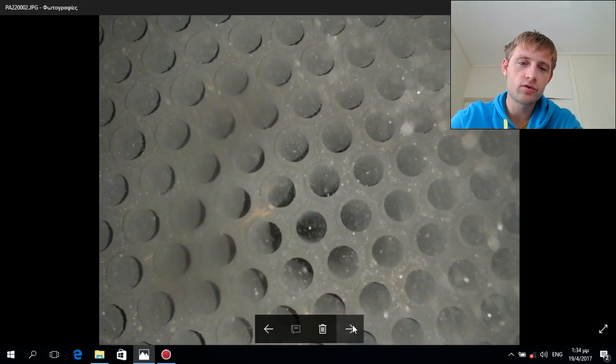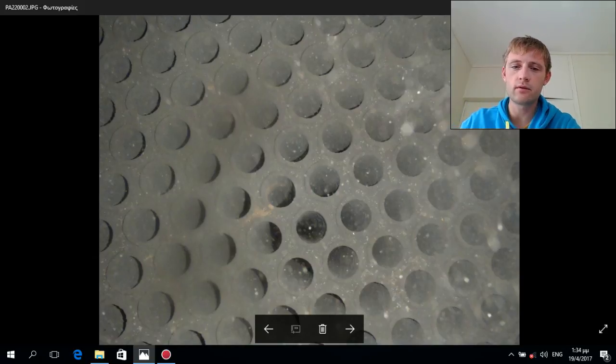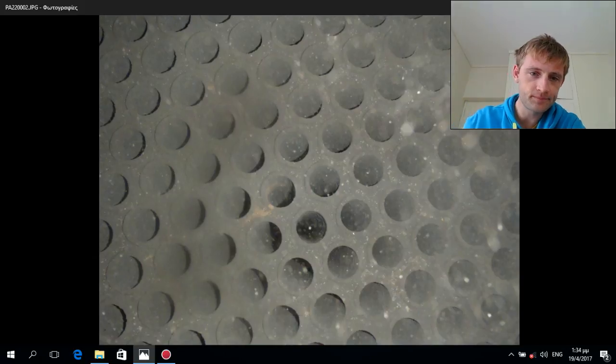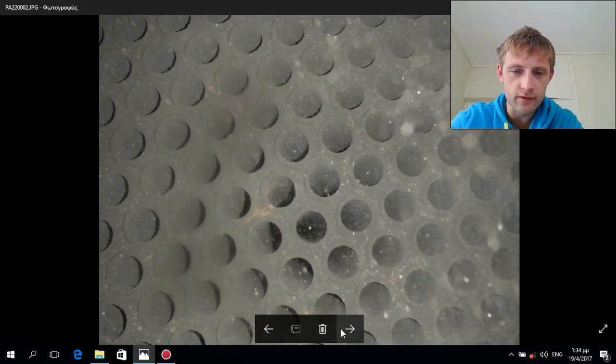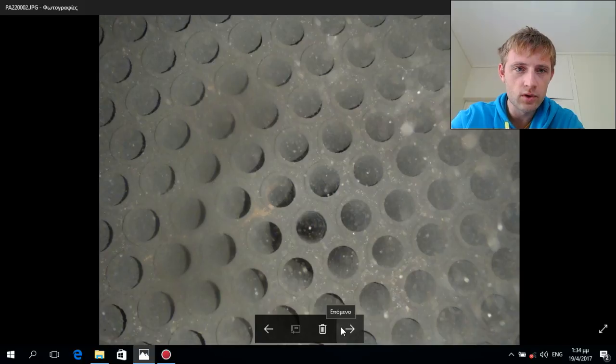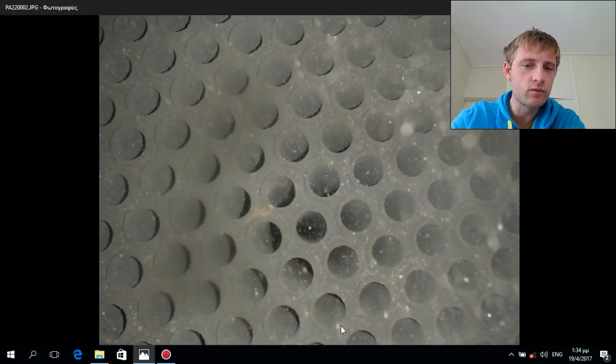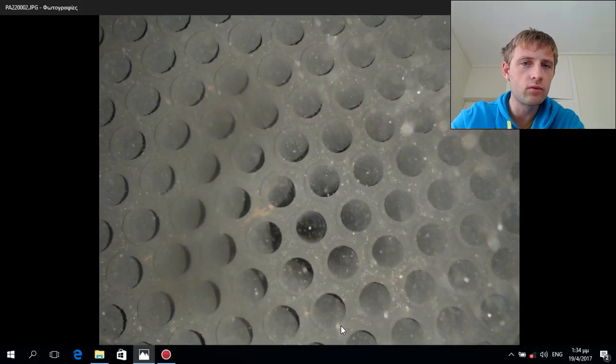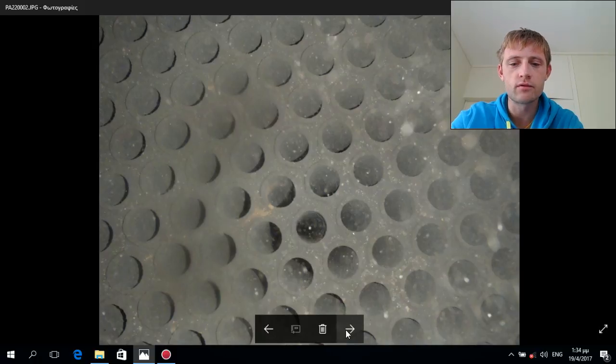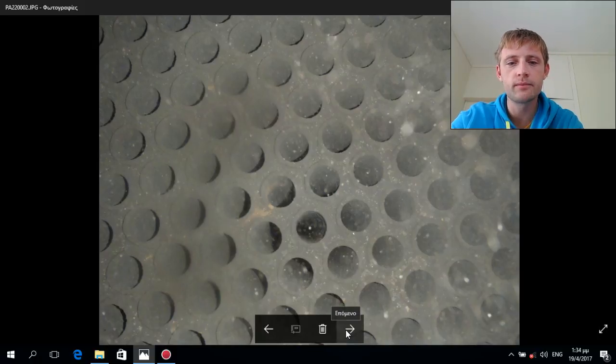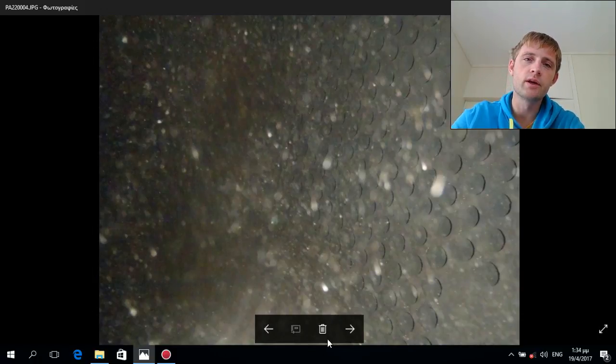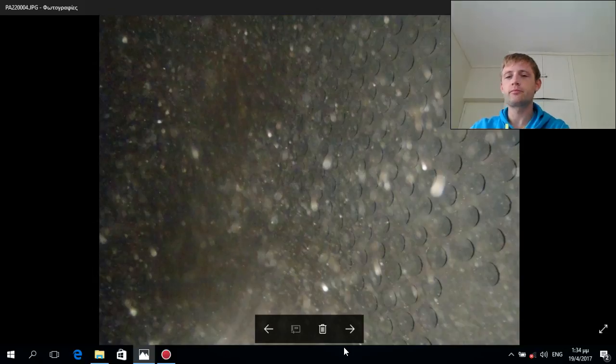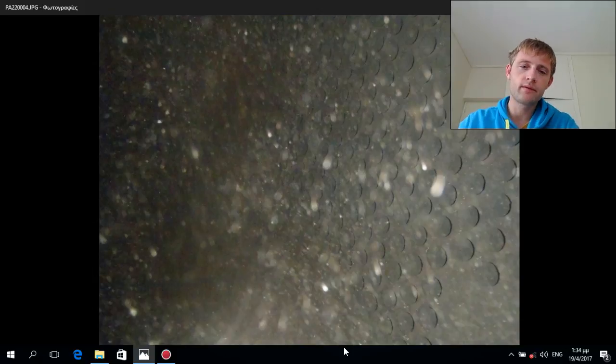Let's see the next picture here. This is from the vertical shoot - you also can see inside the tubes. This kind of exhaust gas economizer was working for two or three months without cleaning, and as you can see there's not so much dirt. It's only the surface which became dirty.